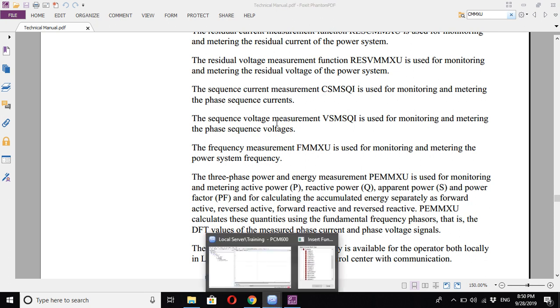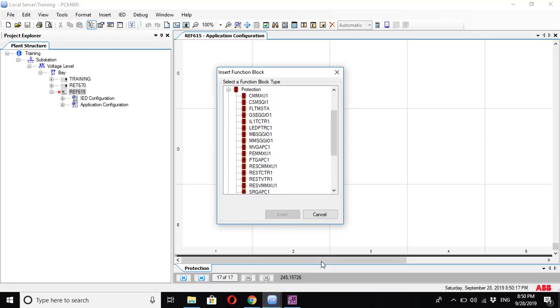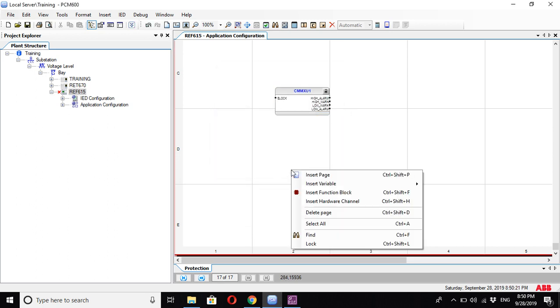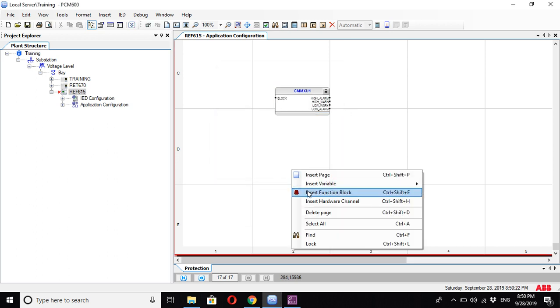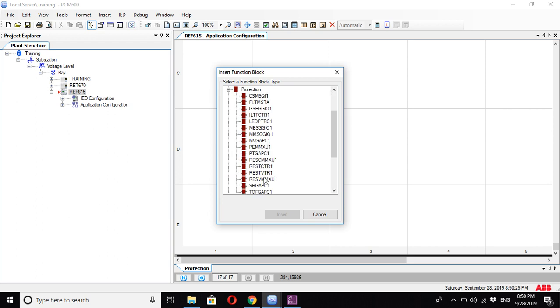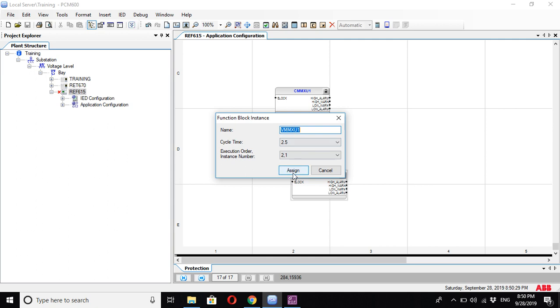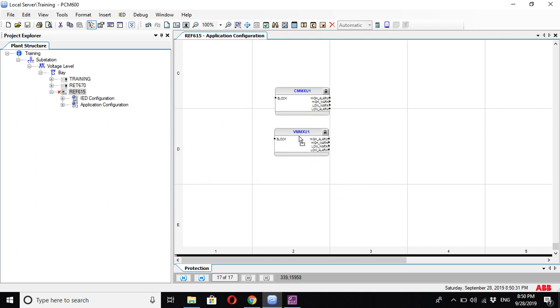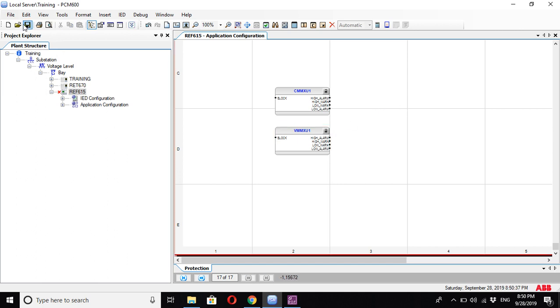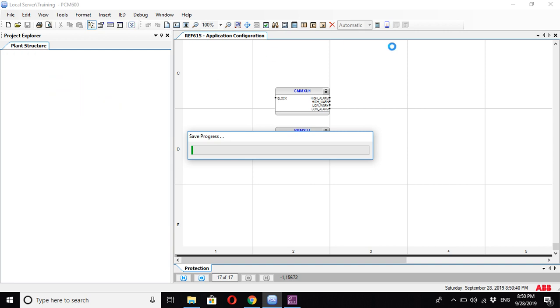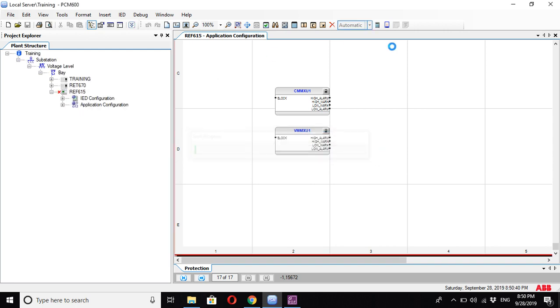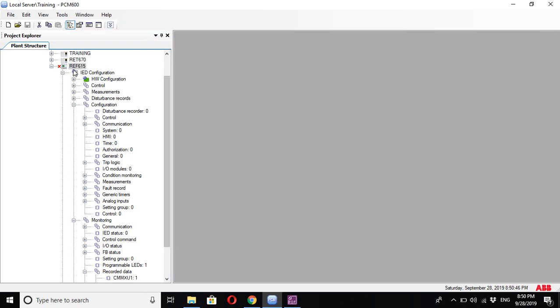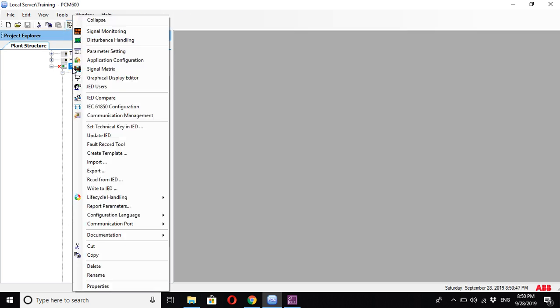So again, we can choose CMMXU and assign it. Insert function block protection, and you can choose VMMXU. This is for the three-phase current; this is for the three-phase voltage, and you can also add the other blocks. After that, save, close this window, right-click, and write to IED.